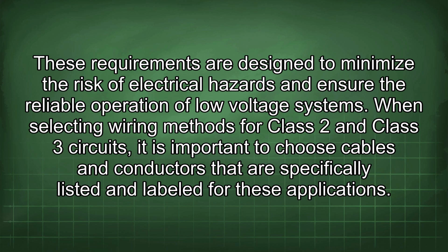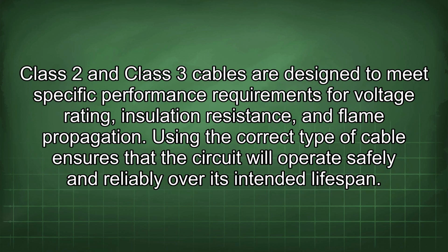These requirements are designed to minimize the risk of electrical hazards and ensure the reliable operation of low-voltage systems. When selecting wiring methods for Class 2 and Class 3 circuits, it is important to choose cables and conductors that are specifically listed and labeled for these applications. Class 2 and Class 3 cables are designed to meet specific performance requirements for voltage rating, insulation resistance, and flame propagation. Using the correct type of cable ensures that the circuit will operate safely and reliably over its intended lifespan.